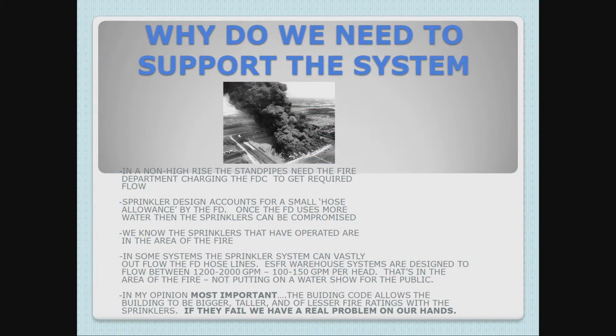In my opinion, the most important thing is that when we build buildings today, the building code allows the building to be bigger, taller, and of lesser fire ratings once it's sprinklered. So the problem is, if the sprinkler system fails, we have a real problem on our hands, a genuine problem. And that's where you get these spectacular fires like the Kmart fire, spectacular fires like there was a cold storage warehouse in South Jersey a few years ago that burned that was just, made the national news. So if that sprinkler system fails, we have fewer safety nets in place.